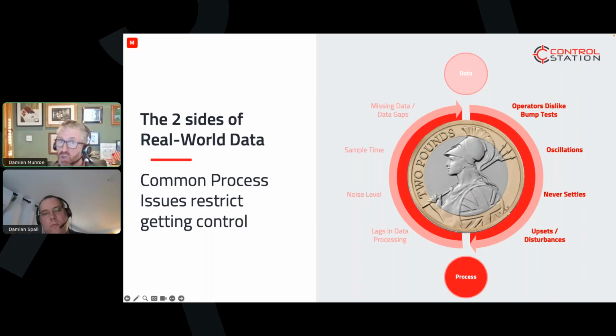So that, and disturbances - it's a mistake to think you can tune disturbances out of your process through PID. Disturbances will always be there. You can attempt to minimize them, but if we think about the process model and the rate of change of our process versus the rate of change of our disturbance, that's the problem. Disturbances that hurt your process are happening faster than your process, so we have to tune very aggressively to try and respond, which means we have a high degree of oscillation in our process.